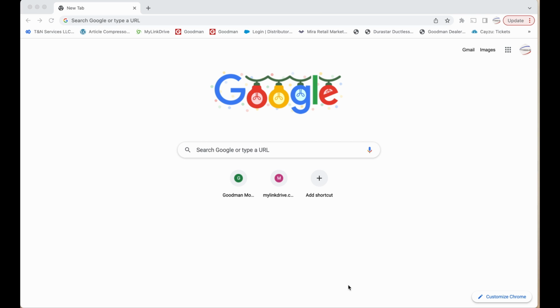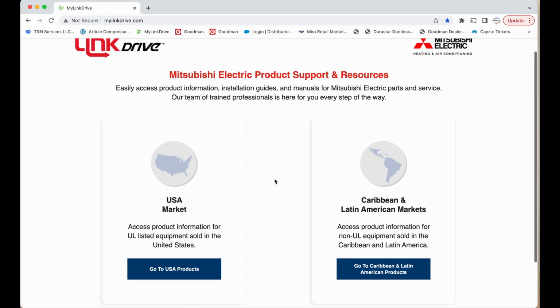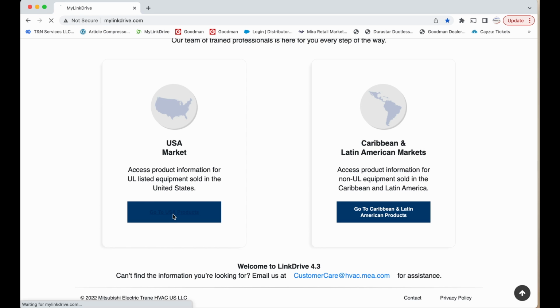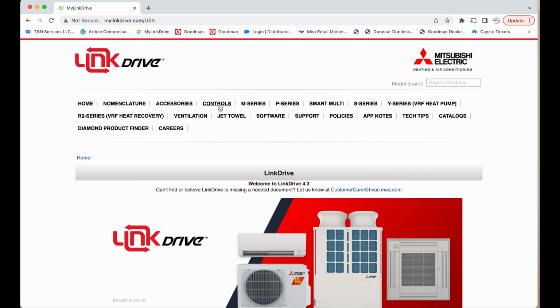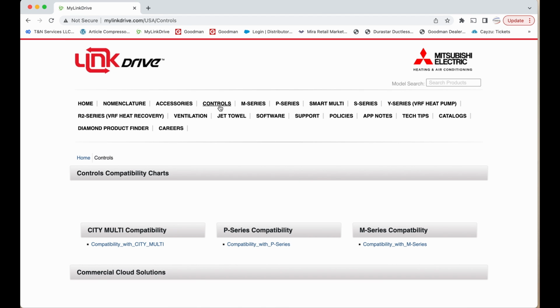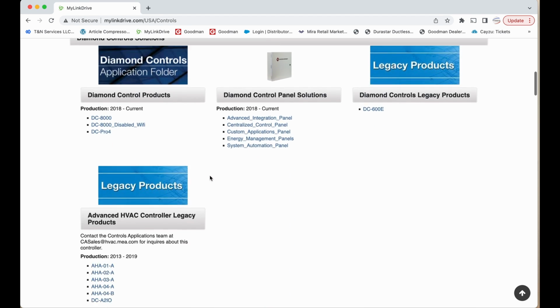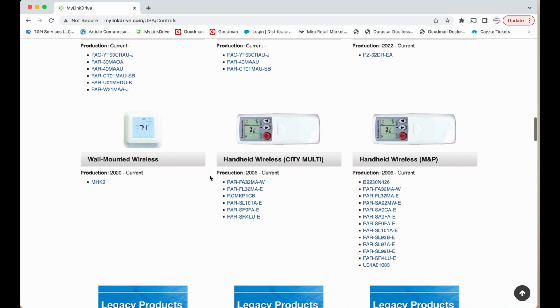All right, let's say you're working on a unit that doesn't have an emergency operation button on it. What would you do? On our ducted system or anything that has the capability of having a wired controller on it, it won't have an emergency operation button, right? So what would you do? So let's go over to MyLink Drive and let's look at the controller. On those particular units, you would physically go into the controller and initiate your test run.